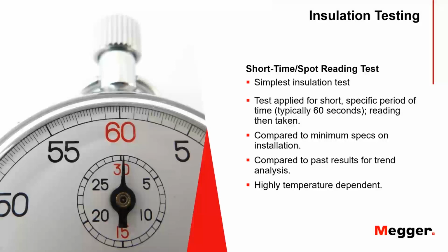Okay, we'll start with the short time or spot reading test. This is the easiest one to do. This is hook up and take a reading. This is what you're doing when you're just doing your go no go type testing. But with long-term testing, this can become a little bit hard to deal with. It doesn't give you sufficient information sometimes, and it is highly temperature dependent.